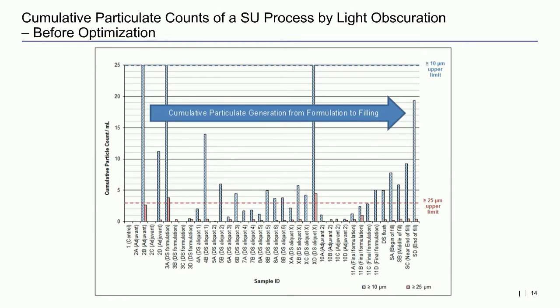The second problem was that we showed that the magnetic force generating the stirring mechanism on the single-use containers was too strong, generating the large particles. And you can see here from the last picture holes in the bags and causing leaking. The third was a result of the peristaltic pump that was used to pass the product, which was chewing the inner wall of the plastic TPE single-use tubing, leading to spallation and particulate generation.